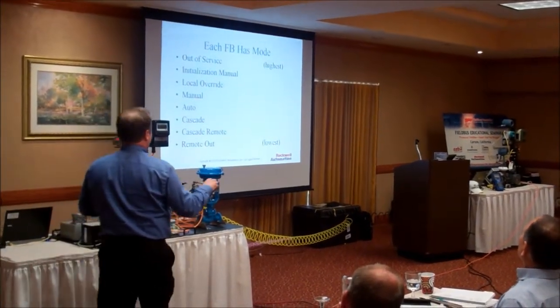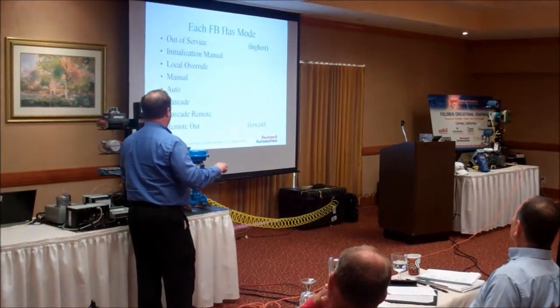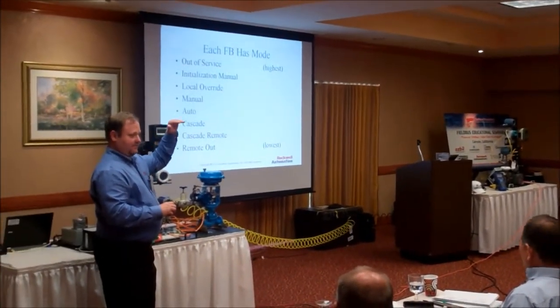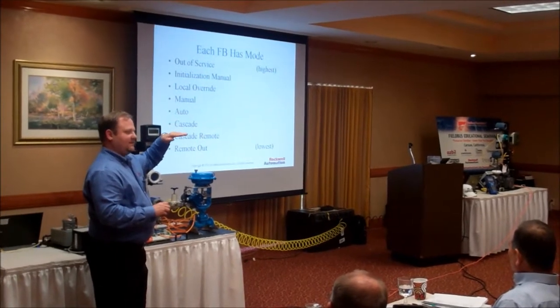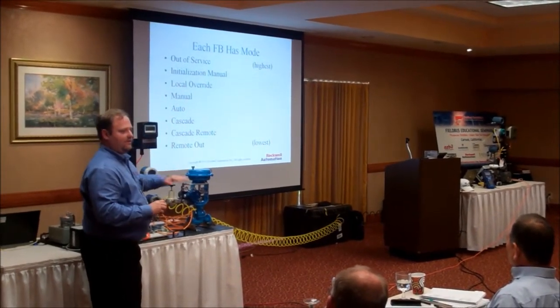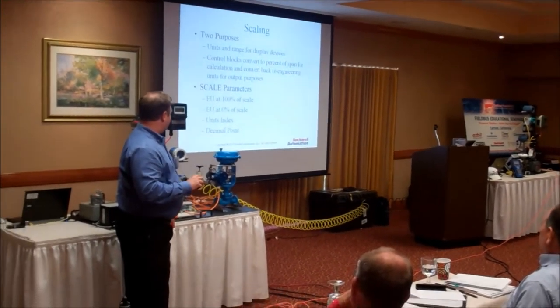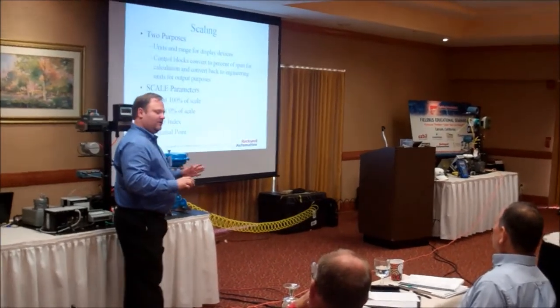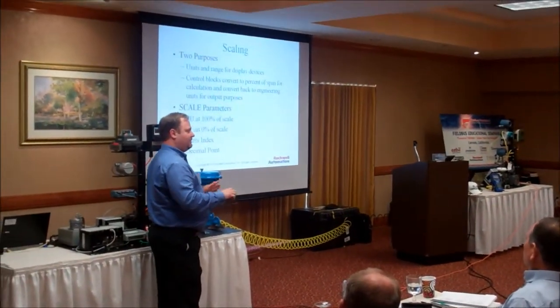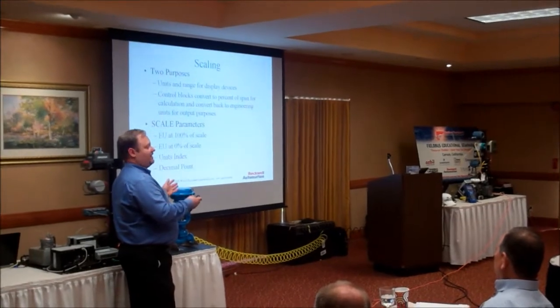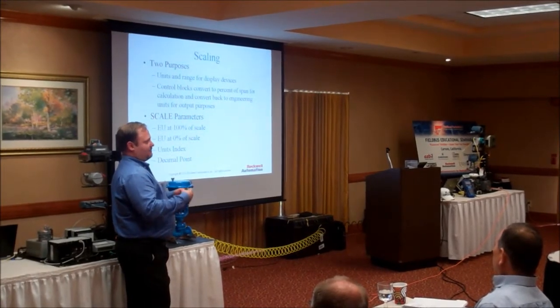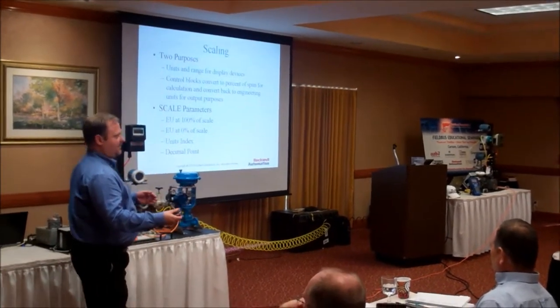Function blocks have modes: out-of-service, manual, auto, cascade. They're allowed from lowest to highest. So if something happens, you get the highest level available; if that highest level isn't available, it goes to the next one down. Scaling: we have to scale the units for PIDs, as you all know. If you have a set point unit of percent, your feedback has to be in percent, so it can calculate the PID properly to give you the proper control variable.